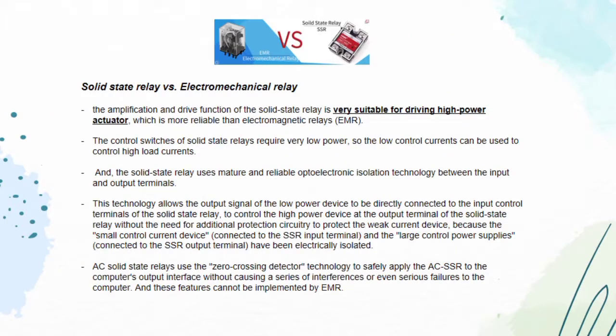The next slide is solid state relay versus electromechanical relay. The amplification and drive function of the solid state relay is very suitable for driving high power actuators, and is more reliable than electromagnetic relays. The control switches of a solid state relay require very low power, so low control currents can be used to control high load currents. And the solid state relay uses mature and reliable opto-electronic isolation technology between the input and the output terminals.